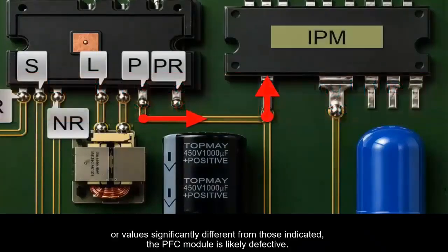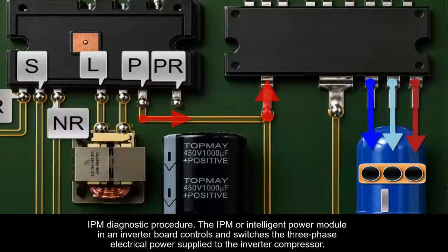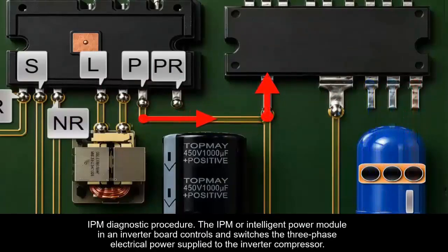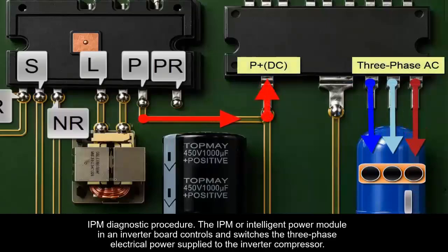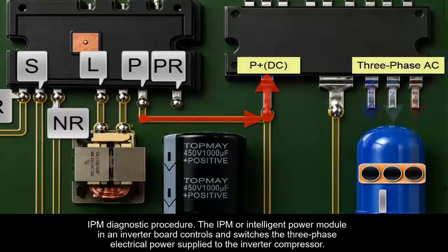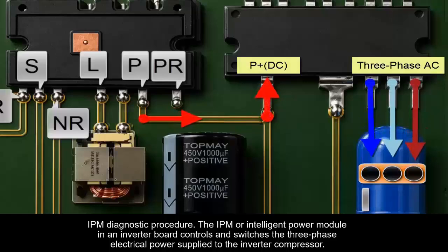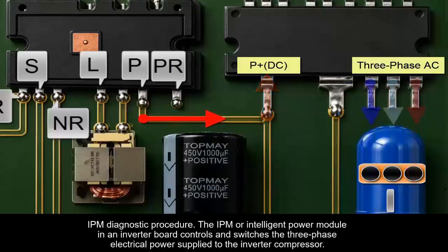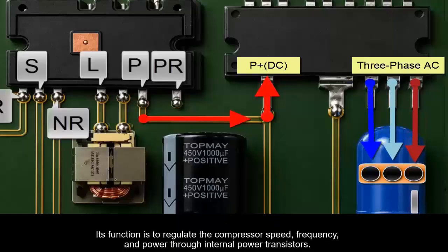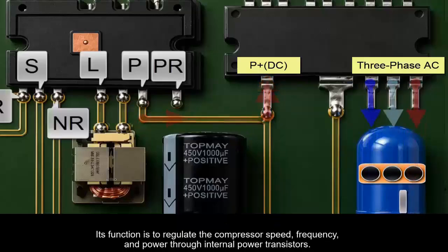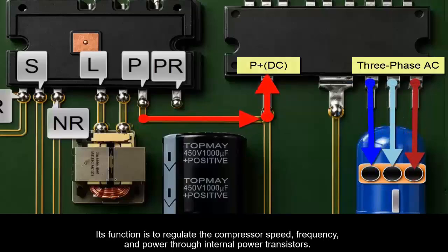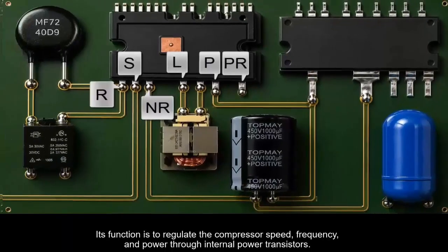IPM diagnostic procedure. The IPM, or Intelligent Power Module in an inverter board, controls and switches the three-phase electrical power supplied to the inverter compressor. Its function is to regulate the compressor speed, frequency, and power through internal power transistors. It also incorporates protection features against overcurrent, overtemperature, short circuits, and low voltage to protect both the electronic board and the inverter compressor.